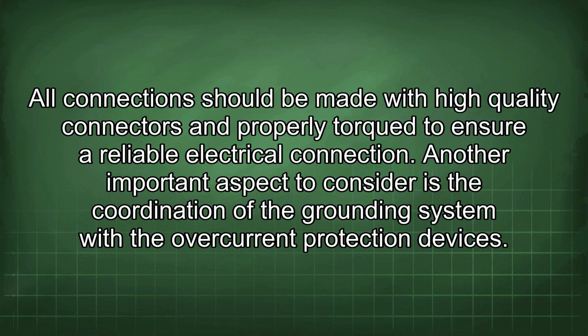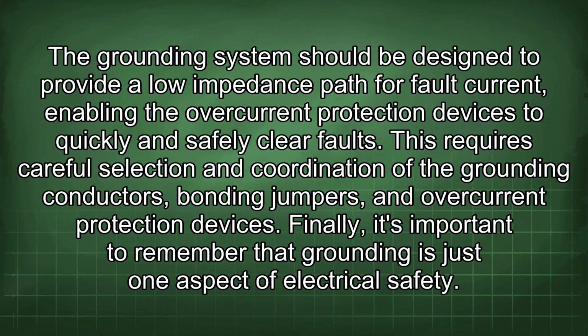Another important aspect to consider is the coordination of the grounding system with the overcurrent protection devices. The grounding system should be designed to provide a low impedance path for fault current, enabling the overcurrent protection devices to quickly and safely clear faults. This requires careful selection and coordination of the grounding conductors, bonding jumpers, and overcurrent protection devices.